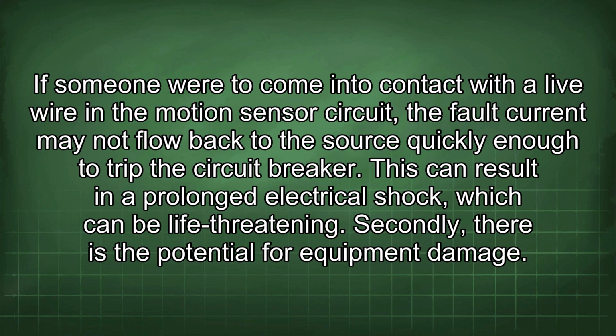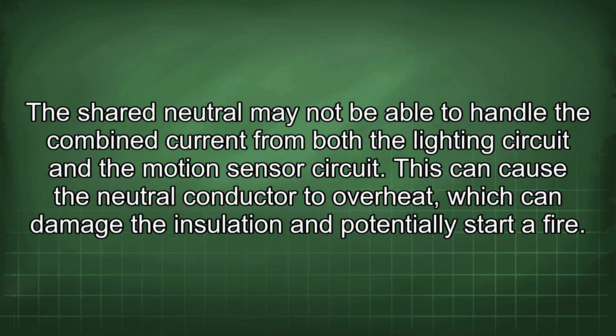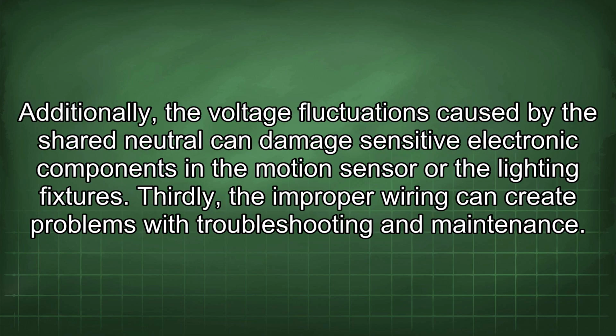Secondly, there is the potential for equipment damage. The shared neutral may not be able to handle the combined current from both the lighting circuit and the motion sensor circuit. This can cause the neutral conductor to overheat, which can damage the insulation and potentially start a fire. Additionally, the voltage fluctuations caused by the shared neutral can damage sensitive electronic components in the motion sensor or the lighting fixtures. Thirdly, improper wiring can create problems with troubleshooting and maintenance.